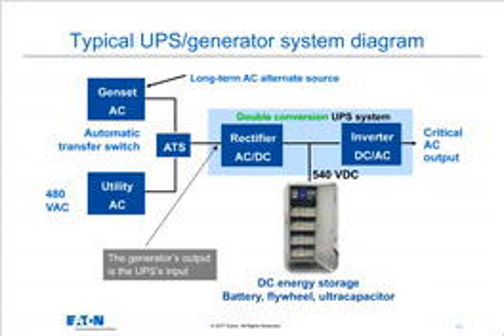Why do we care in the UPS? Well, if we know we're being fed by generator, we may adjust our total harmonic distortion canceling effects in order to optimize for the generator. We may also limit or delay our battery recharge ability until the generator run is over and we're running back from utility power. So we don't use valuable diesel or natural gas in the generator to recharge the UPS batteries. We delay that until after the power event is over. So these are common techniques that you see now.